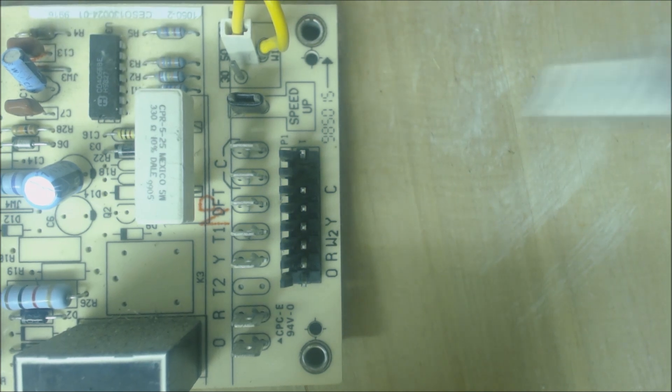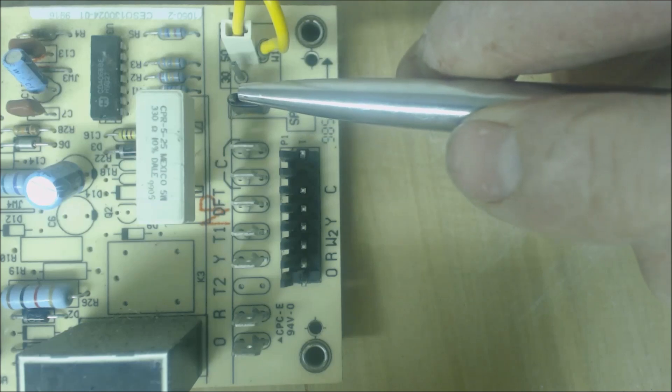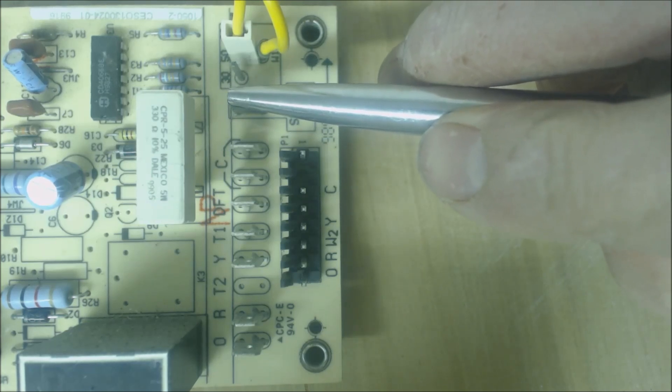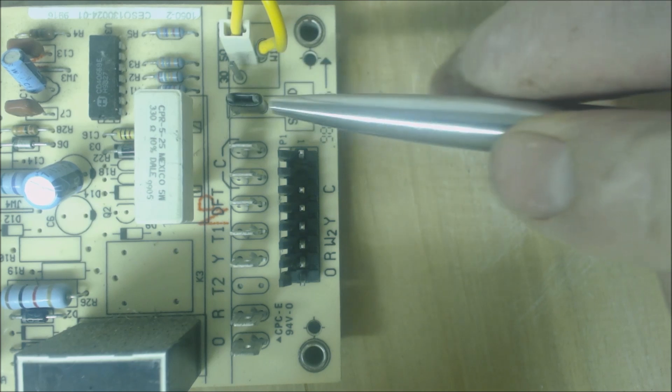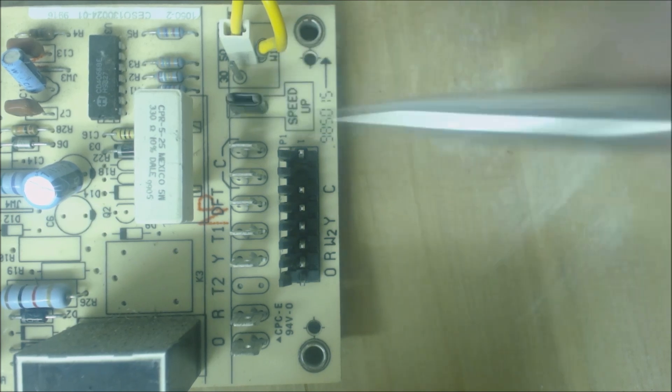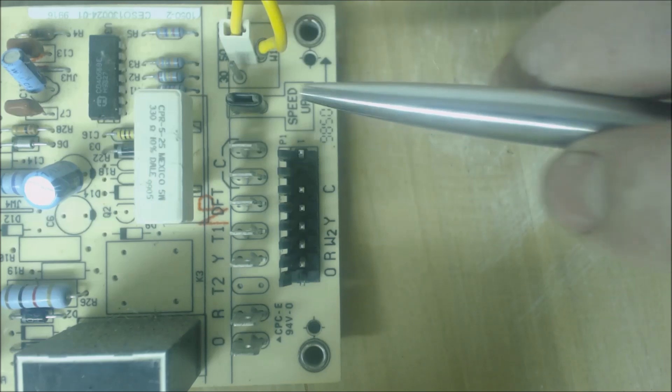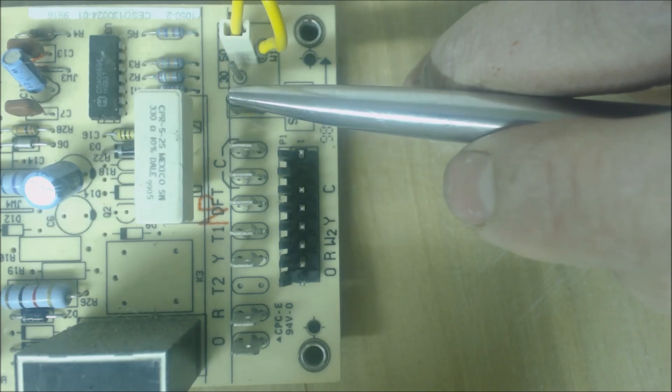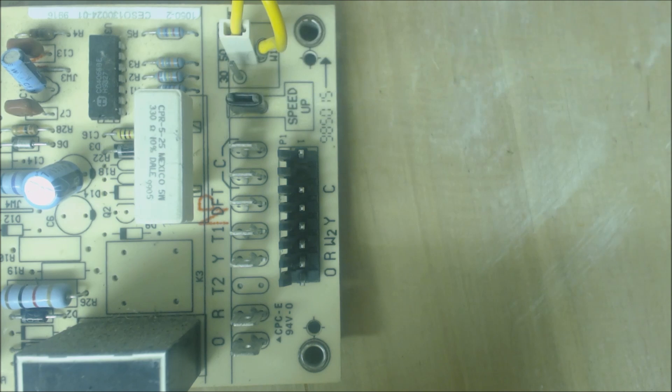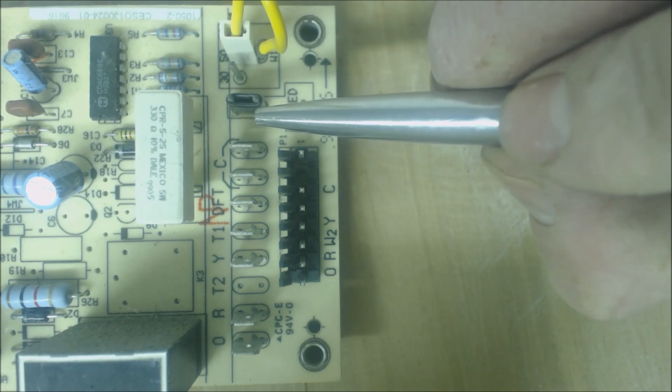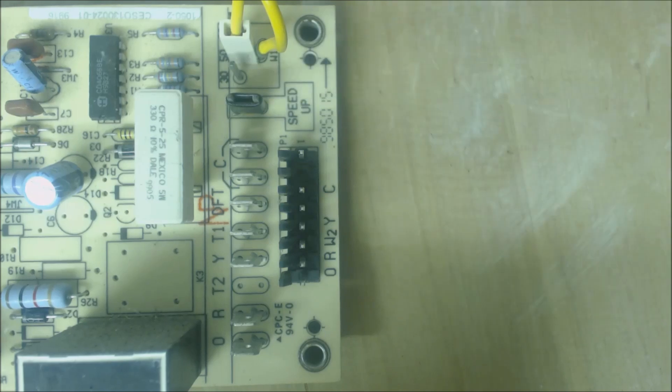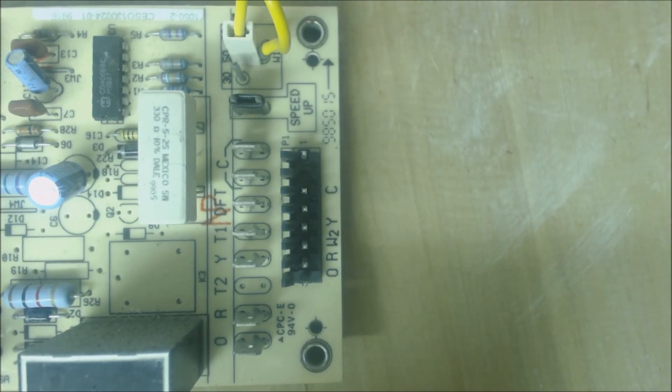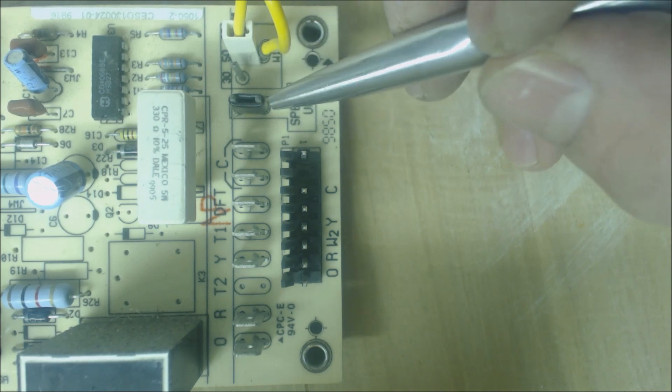After that, you can take a flathead screwdriver and basically short right across these speed up terminals. When you short across these speed up terminals with a flathead screwdriver without any chrome paint on it, it's going to multiply the amount of time that you have the flathead screwdriver on there by 256. So the amount of time is going to be less than a minute compared to this 50 minutes over here. That's how you force it into defrost.